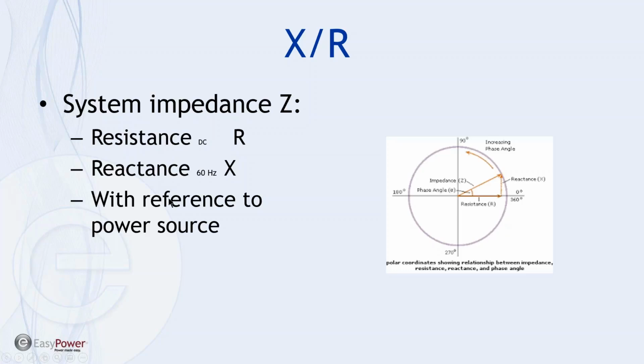And so X represents the inductive reactance, or the system reactance at 60 hertz, and the R represents the DC resistance. And so it's this comparison, and the unit circle is basically the starting point for this discussion in polar coordinates. The resistance will be, in this case, along the horizontal axis, and the reactance will be in the vertical axis, and it's that ratio that we refer to as X over R, and it's that angle, or that phase of that angle, that gives us power factor.